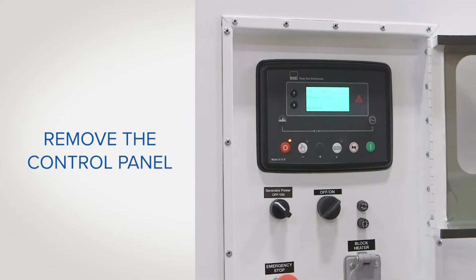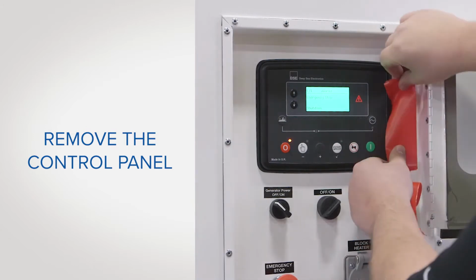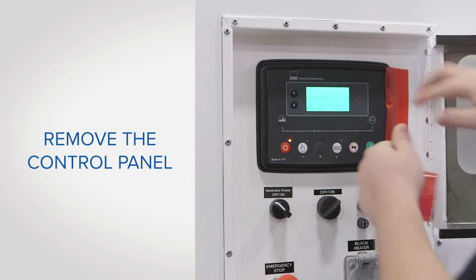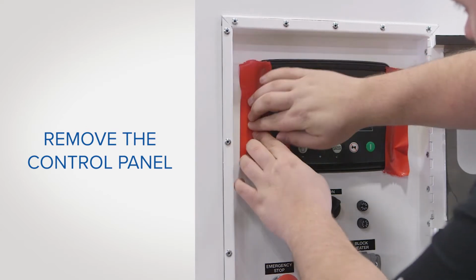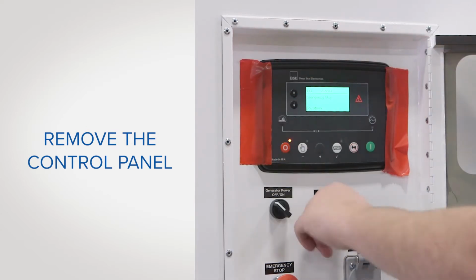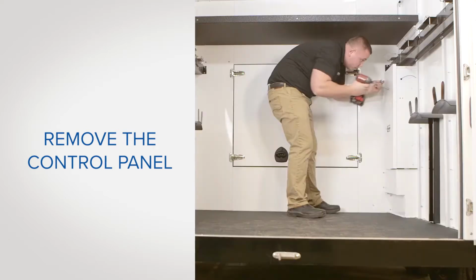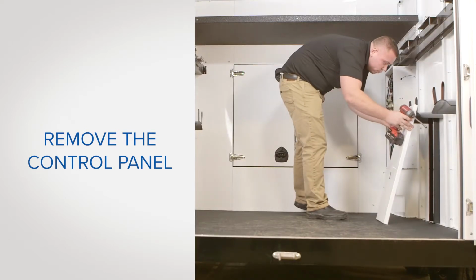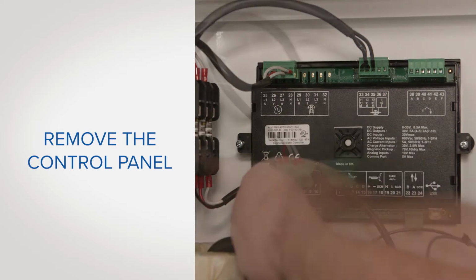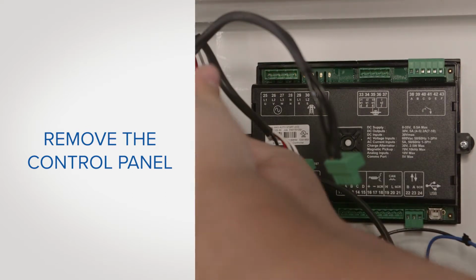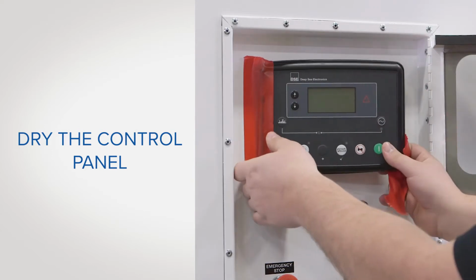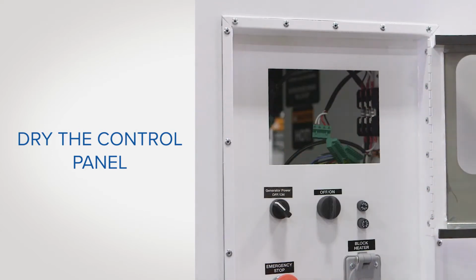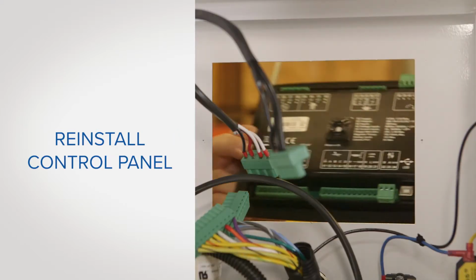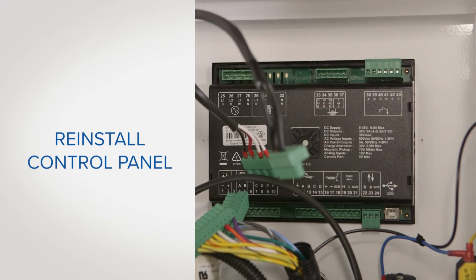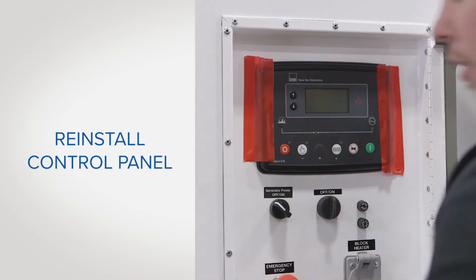To remedy this situation, remove the panel. It's useful to have another person assist you with this process or to hold the panel in place using strong tape, such as the red stucco tape provided with the trailer. Once the panel has been removed, place it on the dashboard of your truck with the blower set on the defrost setting and the heat set on low for 10 minutes. Then reinstall. If this is a recurring problem, you may want to reseal the control box to eliminate moisture intrusion.